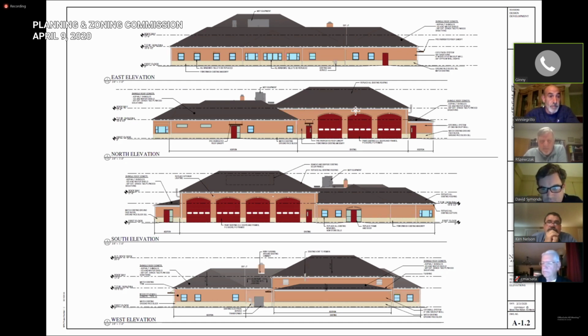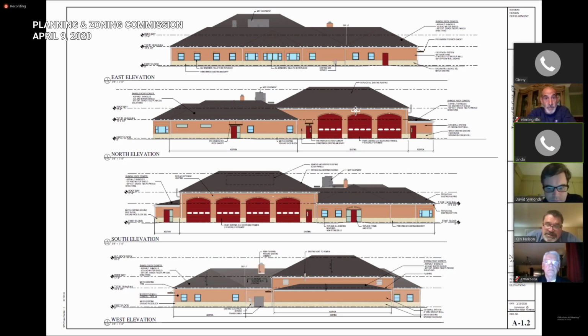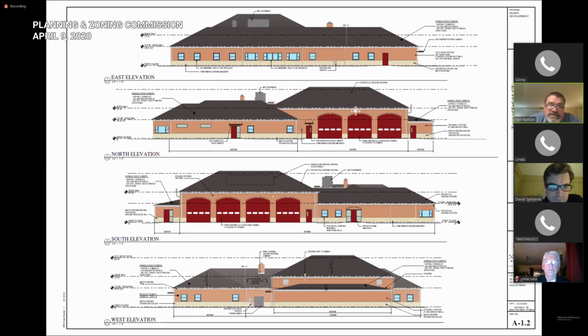I understand your concern between the chimney and the large unit, but wouldn't that be something the building department would take note of if it was a potential problem? Well, we're part of health and safety. If you have a strong enough crosswind and that unit is higher than the chimney, the CO coming out of the chimney is going to blow directly into that unit. I don't care if it's 5 feet away or 15 feet away.